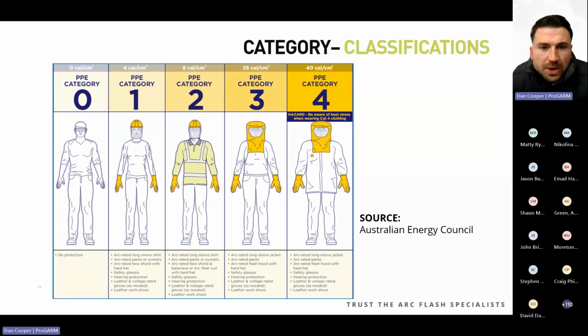PPE can also be categorized based on the cal rating. The Australian Energy Council have put together this infographic that details the required PPE depending on the cal rating. There have been some questions today about HV and LV switchgear, etc. We'd obviously have to look at the specific cal ratings and minimum specifications, but category 1 is 4 cal plus, category 2 is 8 cal, category 3 is 25 cal plus, and category 4 is 40 cal plus.